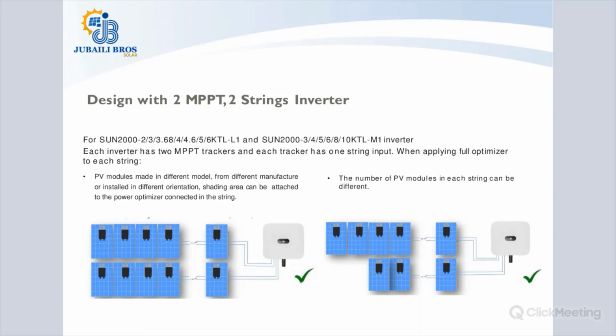In the other case too, this is also very suitable, where you could connect different string lengths to different MPPTs. Remember, these MPPTs are independent of each other. So you could have the situation where you have about 20 modules in MPPT 1, and let's say 70 modules in MPPT 2. I explained here, you could have 20 in MPPT 1 and 2, but in case you have different brand or make of modules, here you can also attach different brand or make of modules, and they will all be optimized accordingly for you. So this is what the optimizers can actually achieve for us. Let us move a step forward.